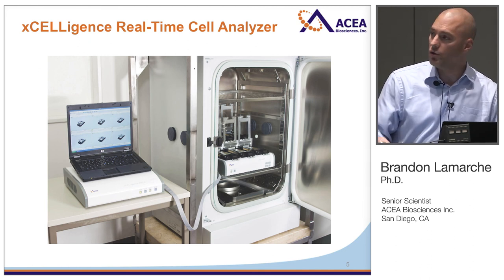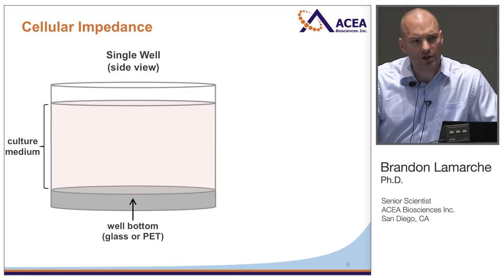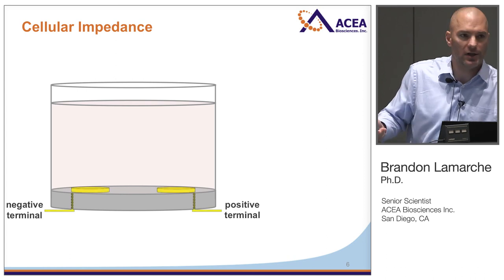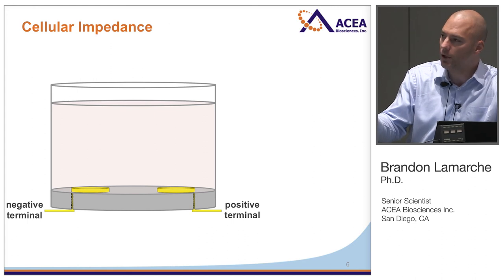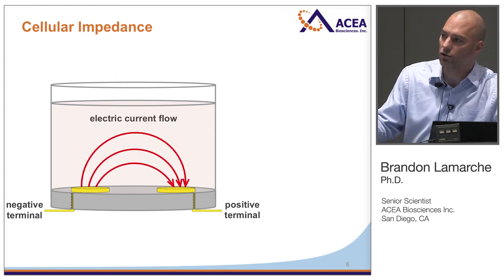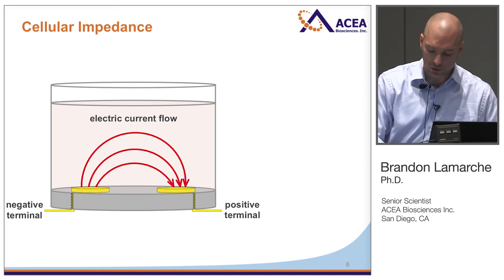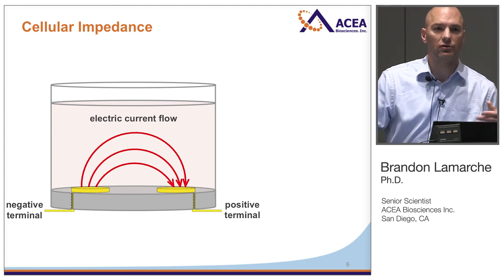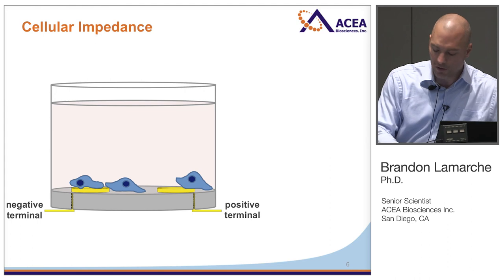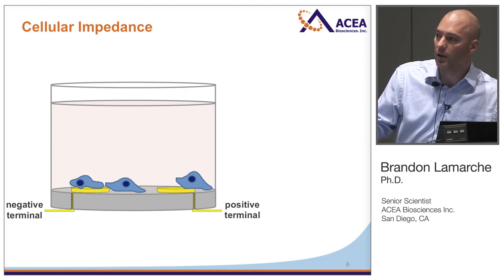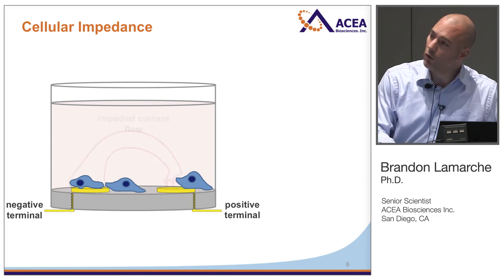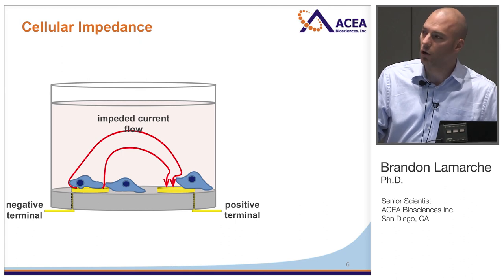The instrument interfaces with a computer where you program your experiment, acquires data in real time, and you do your analysis there as well. To understand what xCELLigence is monitoring, zoom into a single well: the well is immersed in media with gold electrodes integrated into the bottom. When the plate is inside the xCELLigence instrument, a very weak electric potential is applied across the bottom, causing a current to flow from one electrode to the next — electrons hopping through bulk solution. This background measurement is made in the absence of cells. Once cells are added and deposited onto the bottom, they take up surface area on those electrodes; cells conduct electricity much more poorly than the surrounding medium, causing an inherent resistance or impedance to current flow.